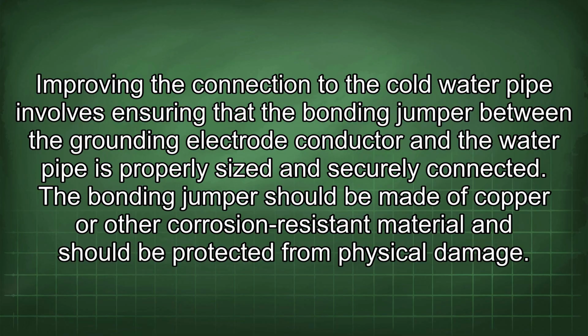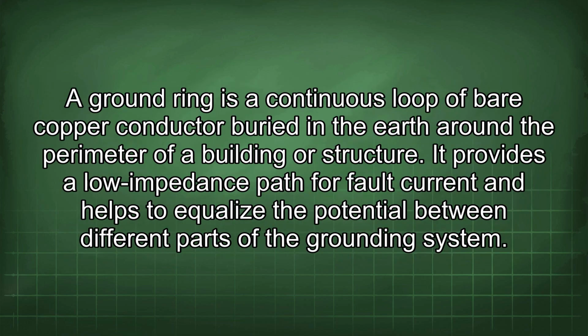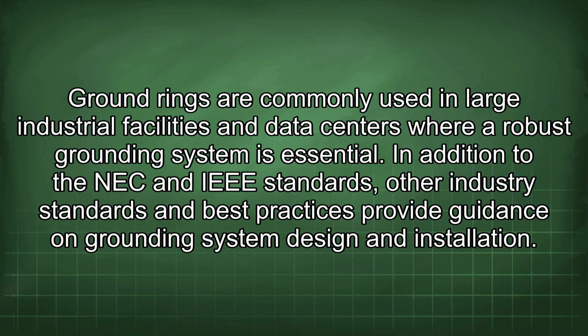The bonding jumper should be made of copper or other corrosion-resistant material and should be protected from physical damage. A ground ring is a continuous loop of bare copper conductor buried in the earth around the perimeter of a building or structure. It provides a low impedance path for fault current and helps to equalize the potential between different parts of the grounding system. Ground rings are commonly used in large industrial facilities and data centers where a robust grounding system is essential.